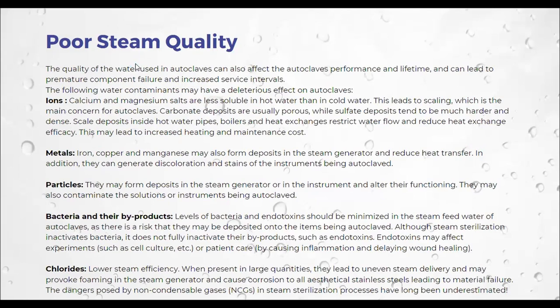All right, thanks, Janita. So when it comes to poor steam quality, I can sit here all day and talk about it. Poor steam quality, mainly you look at water, poor water quality. If you have poor water quality, you're going to have a problem with your steam quality. Poor steam quality may impair the sterilization process, can have a negative effect on equipment, and limit the types of loads that can be sterilized. For this reason, we suggest maximum purity levels of the feed water to the autoclave.